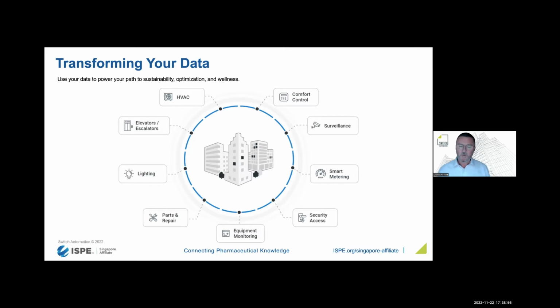So what you need to do is break down those silos, bring all of your data into a single source, then normalize it and build up the relationships so you understand the connectivity between a terminal VAV unit in an office space and the air handling unit providing air to it, and the chiller or boiler providing heating or cooling to that air handling unit - so you can look at the data holistically, as opposed to just at a room thermostat level, which is how it's done today.